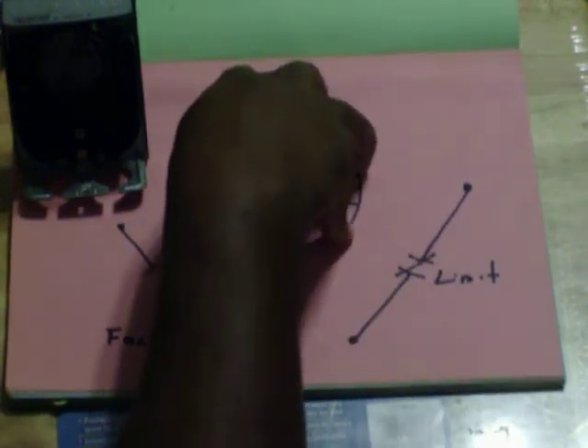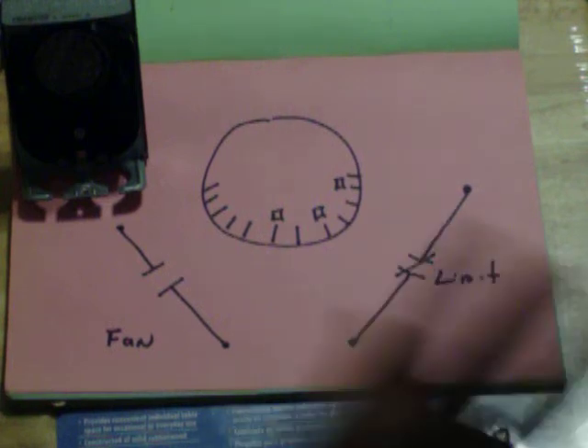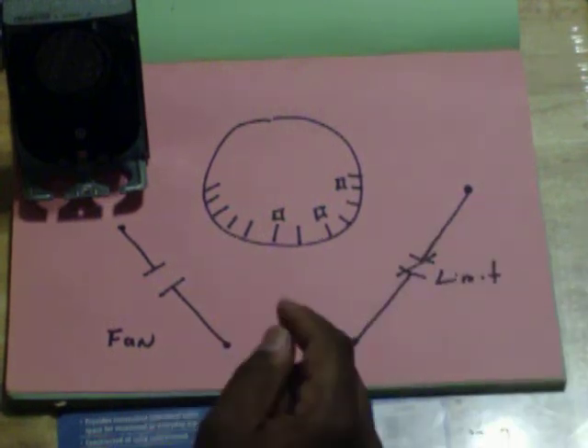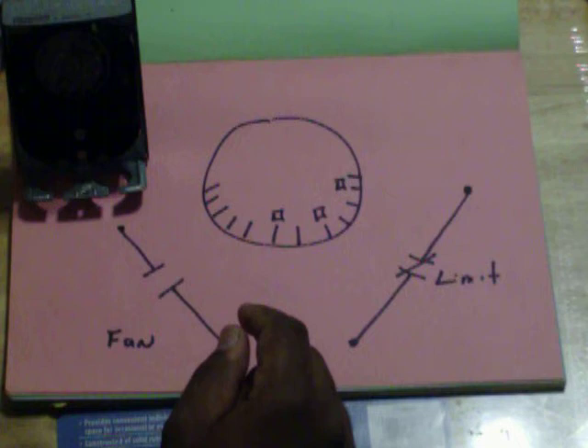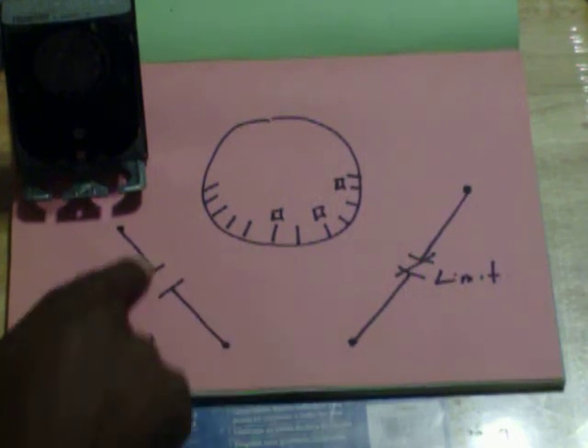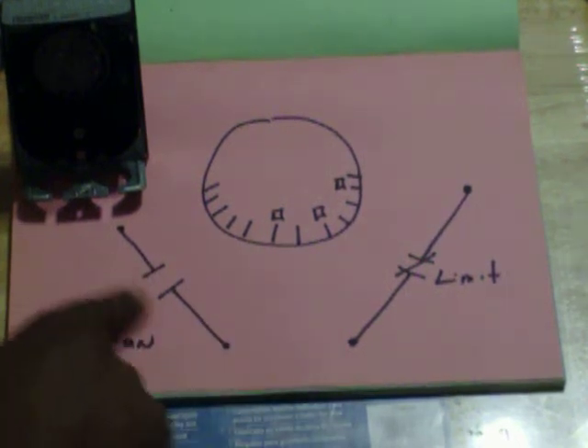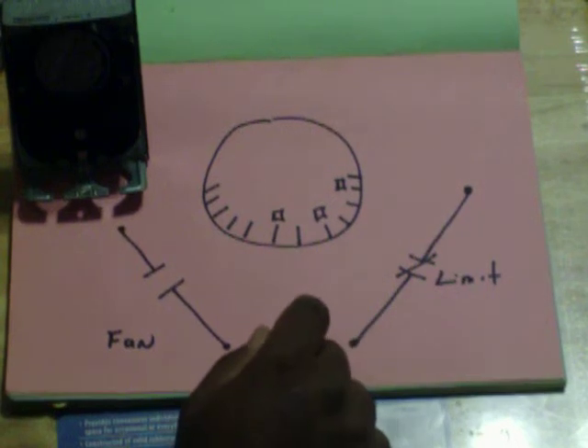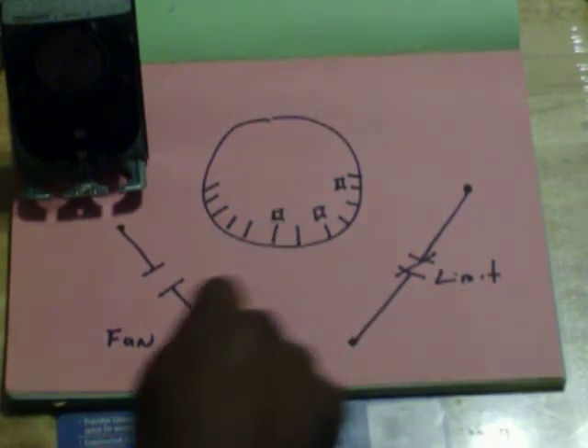That way, if this mechanism failed, you would shut off your thermostat. It wouldn't allow anything to come on. Now, coming off of your low speed of your blower, you'd come to the fan to here, to your fan side, and then go to the other side of power. What that does is, when this gets to a certain temperature, this closes and brings on your low speed.